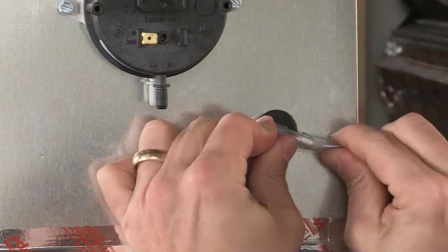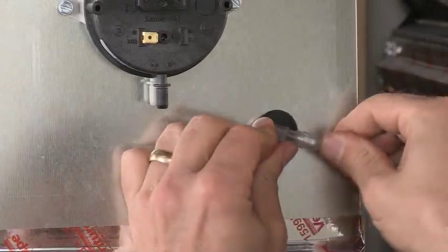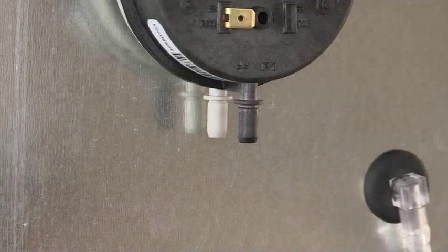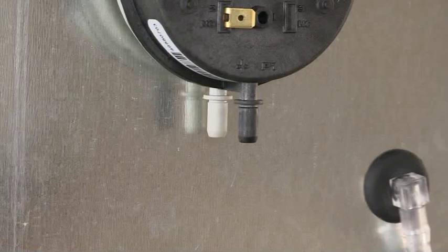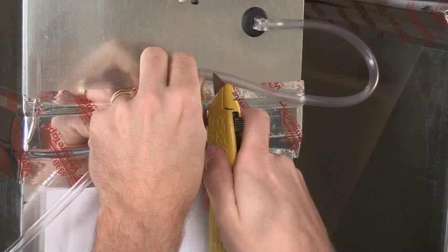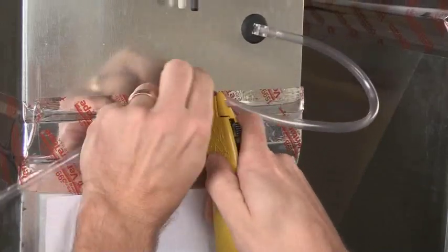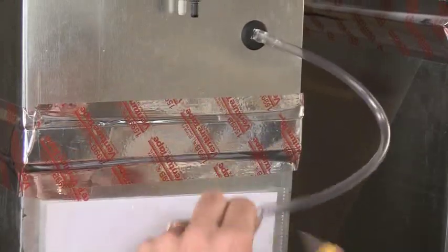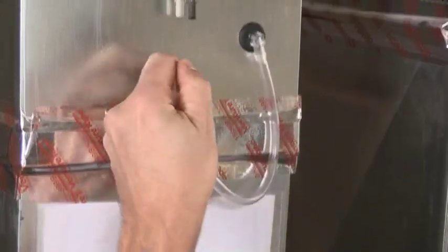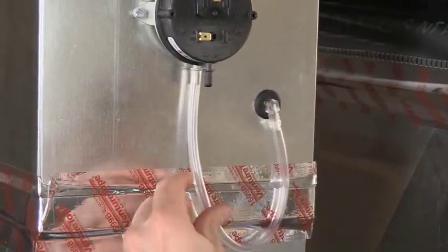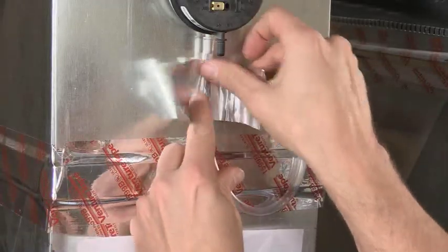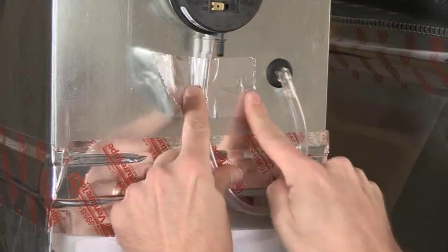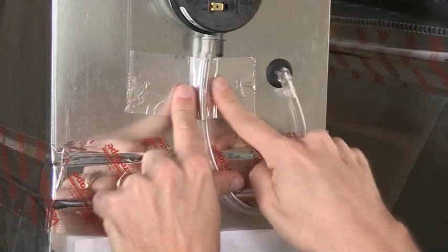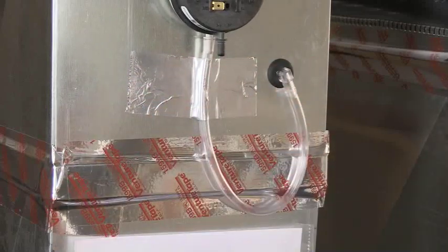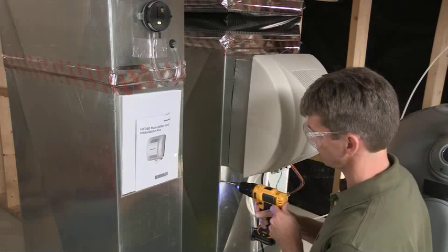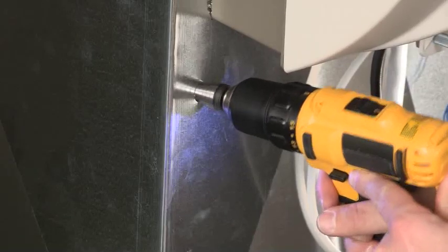Connect the tubing to the tubing fitting elbow. Connect the other end of the tubing to the applicable pressure connection on the switch. The tube that runs to the return duct needs to be attached to the gray port. You may cut the tubing to fit the connection length between the elbow fitting and the switch. It is also recommended to secure the hose to existing structures to avoid accidental disconnection. The tube that runs to the supply duct needs to be attached to the black port.